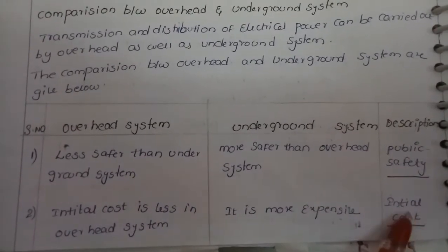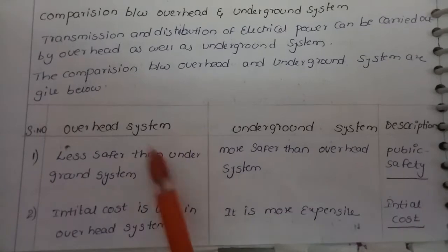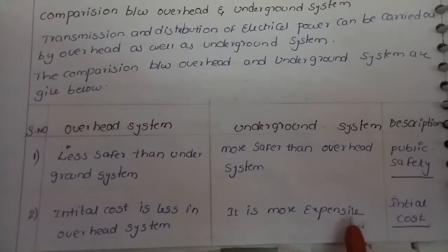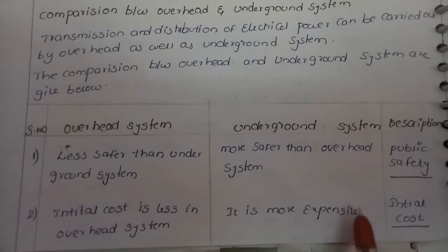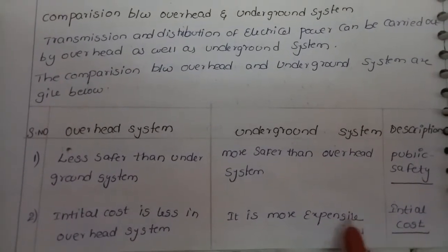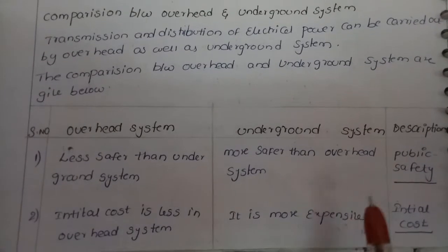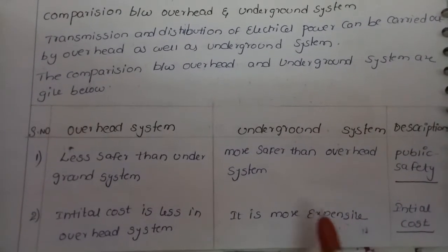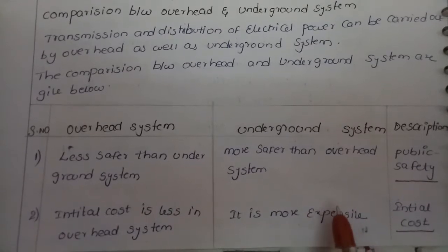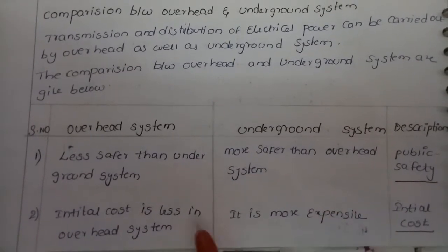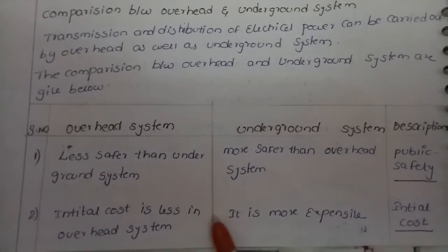Regarding initial cost, overhead systems have less initial cost. Underground systems are more expensive because we have to dig a channel, construct the cables, place the cables, and provide insulation. Therefore the underground system is costlier — approximately 10 times more costly than the overhead system.